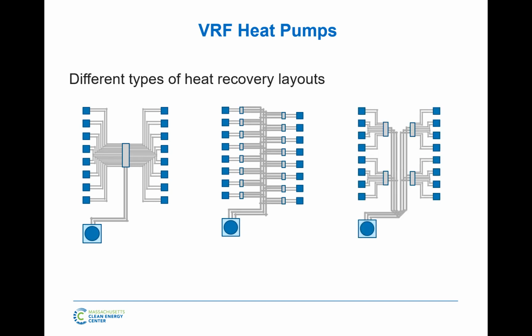So like I said, in heat recovery, different manufacturers do it differently. This on the left is a 2-pipe system where they actually do the whole thing with 2 pipes to the main central larger branch control device. 3-pipe manufacturers can use a mix of single branch control devices at each unit, usually more common for multi-res, mid-rise, high-rise buildings, or a mix of both. It's 3 pipes, but they use multi-port branch boxes. Everyone's got their pros and cons. Everyone's going to look at your building and optimize which method to use depending on what. Some manufacturers can use multiple of these. Some are limited to one. That all depends on the manufacturer.